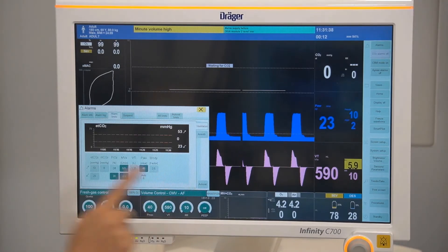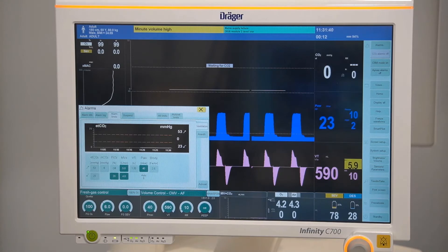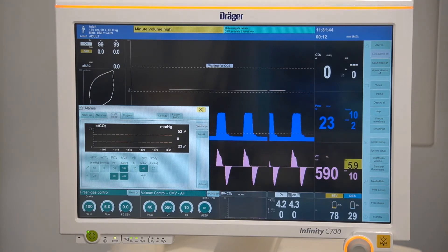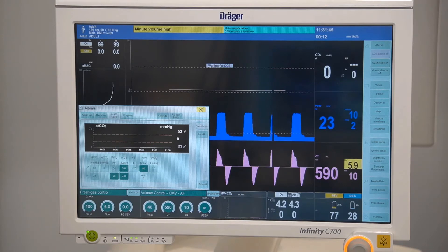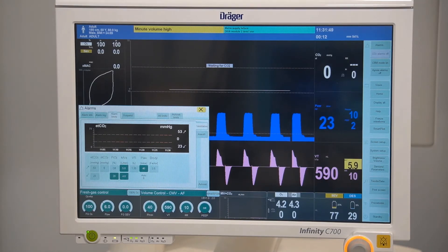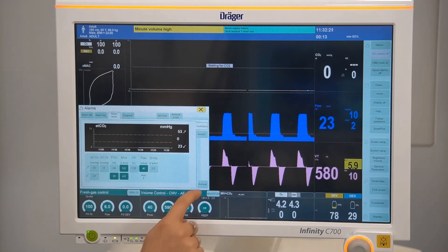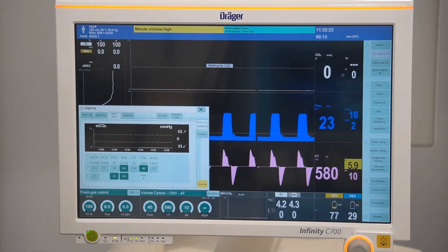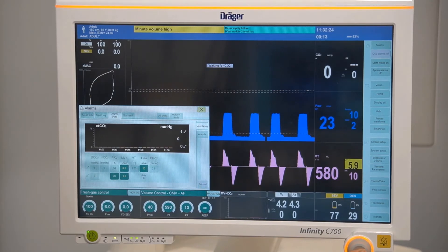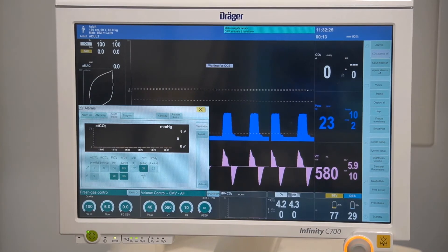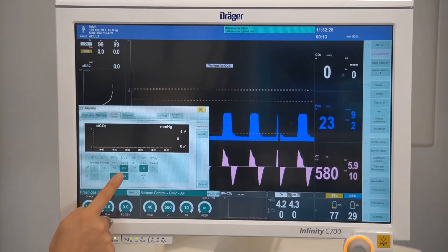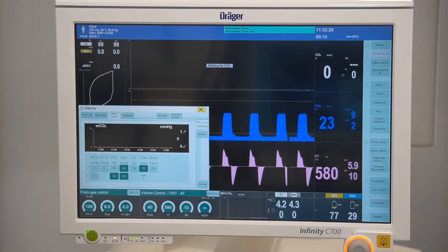The auto set button allows alarm limits to be set to current measured values and will readjust limits to a configured percentage above and below the current measured value. To auto set alarms, select the button and confirm with the rotary knob. Here you can see the alarm limits have automatically been adjusted to current measured values.